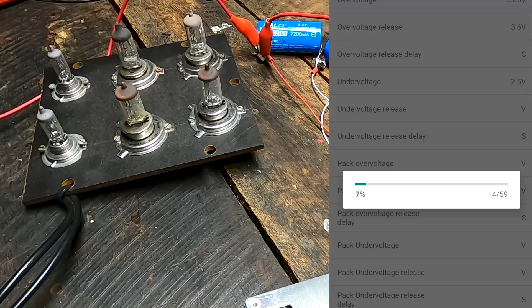Let's check the parameters again here inside the settings. Why is this so complicated? It's just a piece of shitty software. There, charge over current 1.2 amps for 10 seconds, and then we've got a release after 5 seconds again. The discharge over current works, but not the charge current.